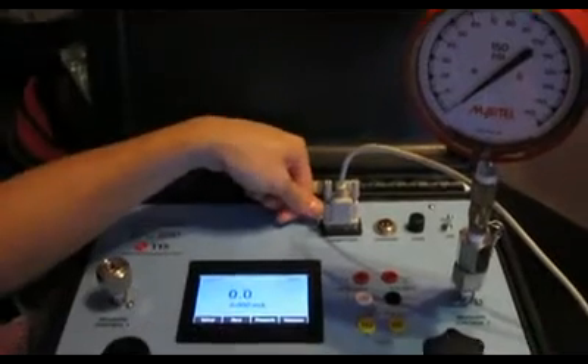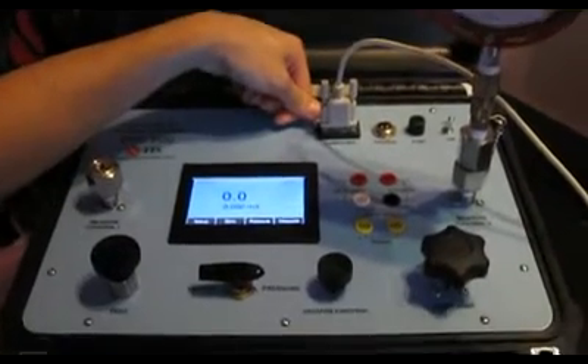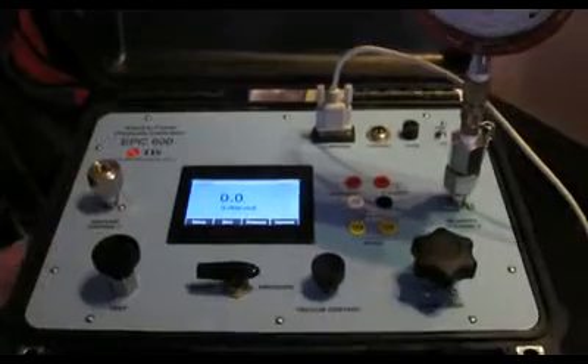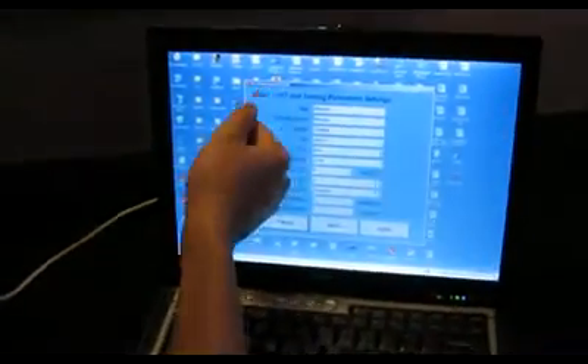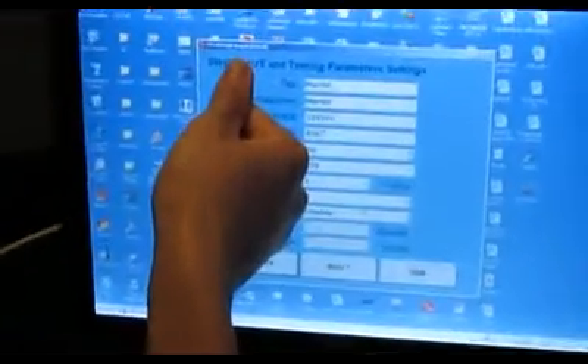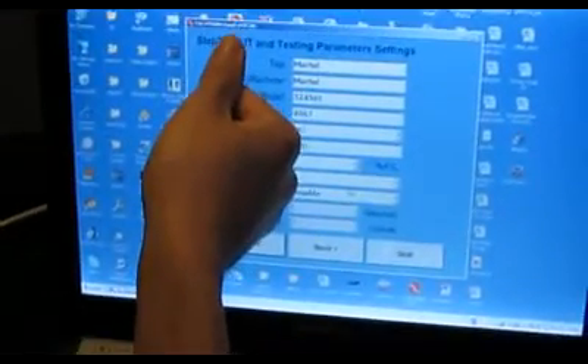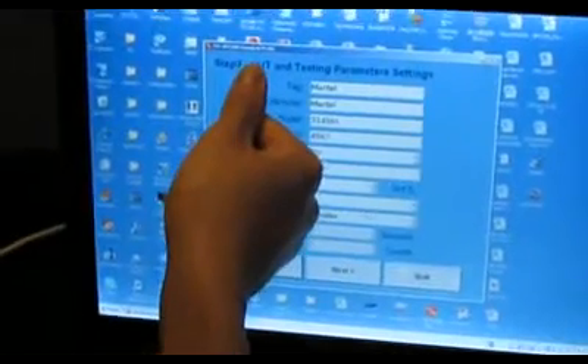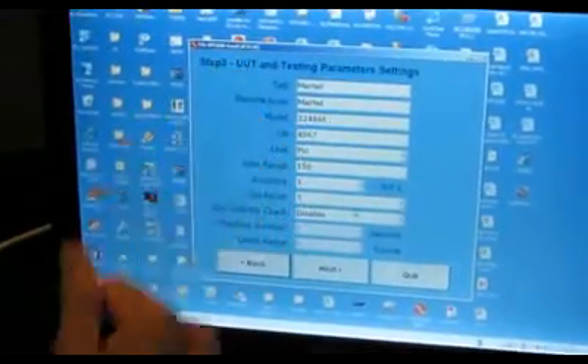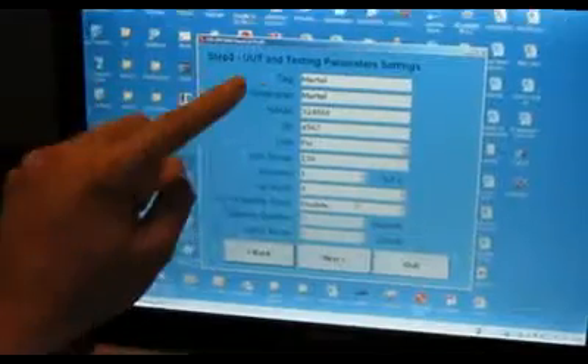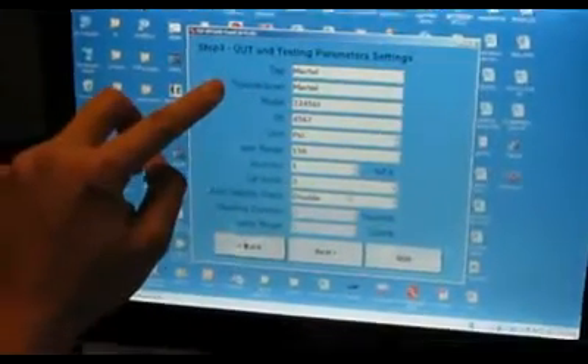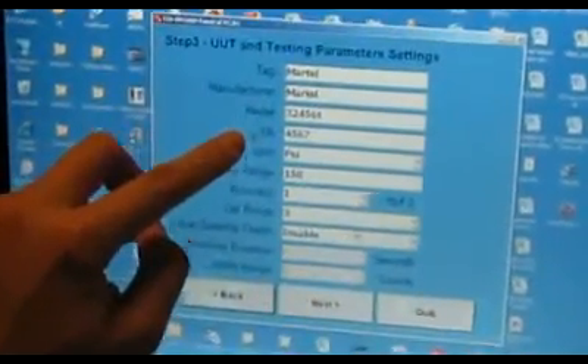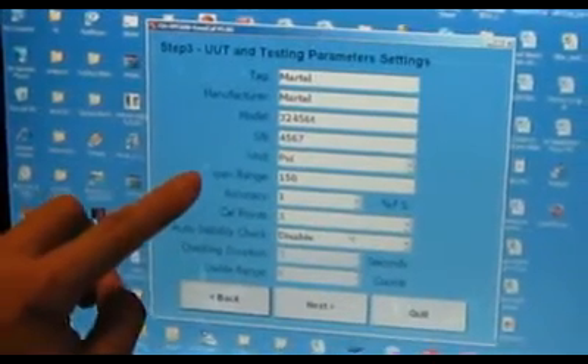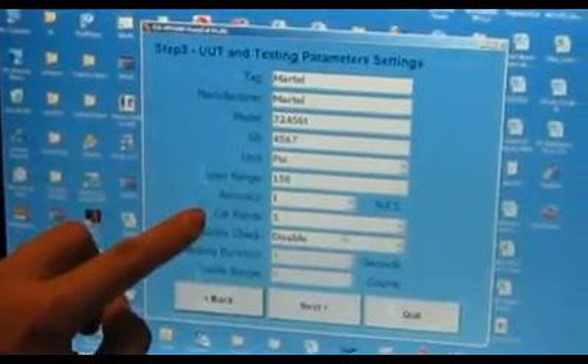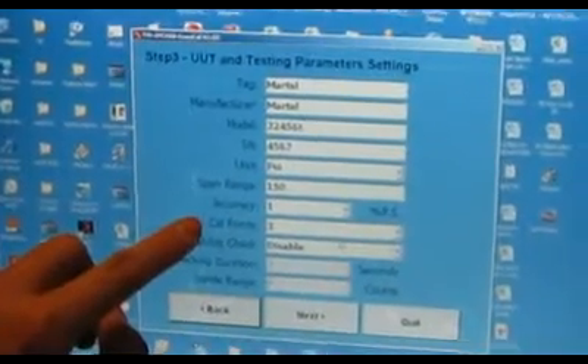If we link it up with a computer via the RS-232 port, we are able to use our EPC600 EasyCalWare. This EPC600 EasyCalWare is able to generate a certificate and save it in Excel or PDF. We simply need to key in the tag name, manufacturer, model number, serial number, unit, range, accuracy, and cal points of the gauge that we want to calibrate.